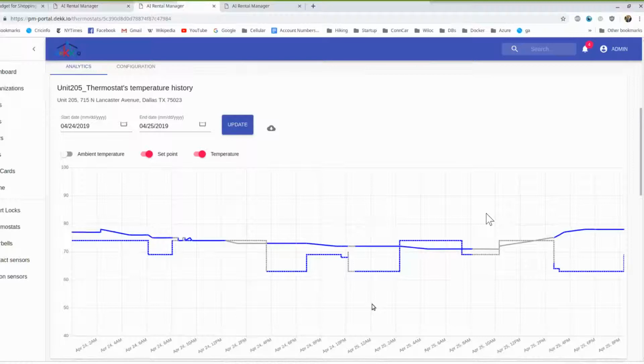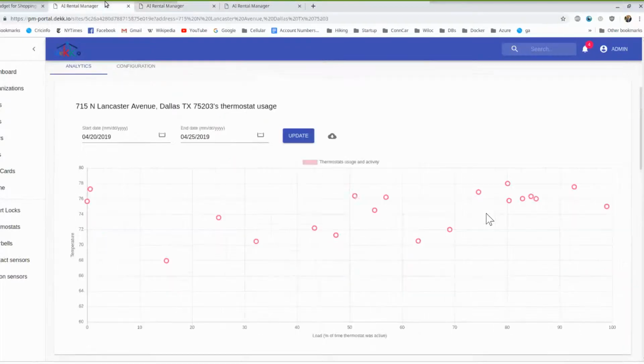Right, and the other thing, at least for me, the very useful feature was that in the units where the AC is not working well, the difference between set point and the temperature in the unit is larger compared to the other units. So I would know that there's a bad AC unit far before it goes bad. And that's what the analytics that Badri was showing is summarizing. There are two aspects that were very useful in my properties: one is being able to control the temperature.